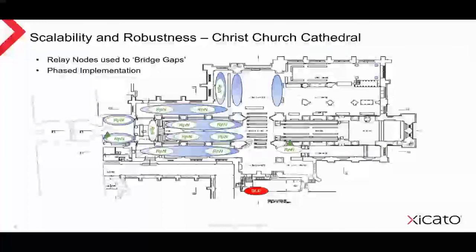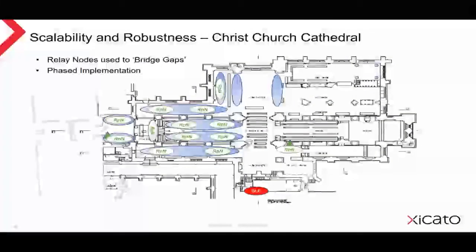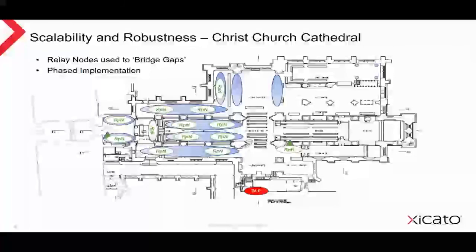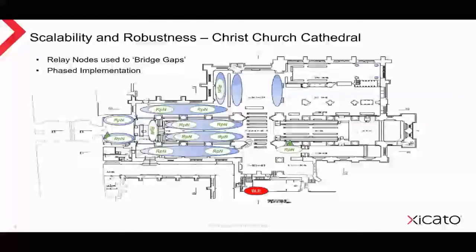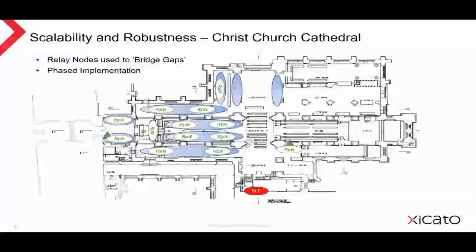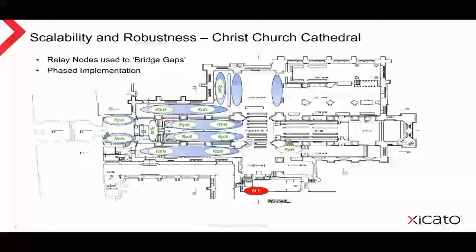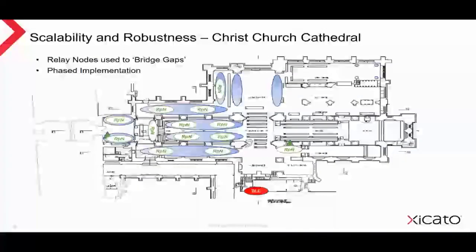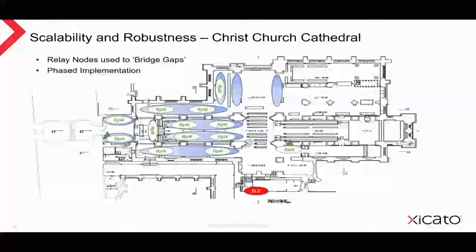Unfortunately, however, we found out, being on site at the installation, that some of the Bluetooth drivers for the north transept lighting had to be sited remotely in a cupboard on a mezzanine level behind a stone balustrade. It's the red ellipse shown here. There was in fact no Bluetooth communication between this location and the main body of lighting, and any chance of achieving connectivity to the lights in the Latin Chapel also had to be removed.